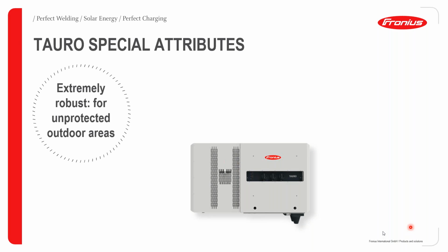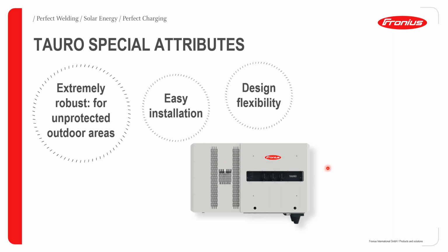So what can we say about the Tauros as far as the special attributes are concerned? Just to highlight for you, first of all, the Tauros is extremely robust, and this is for unprotected outdoor areas. As I mentioned before, the design of the Tauros inverter is very different from the SnapINverter series. The front cover, or the front area, is a double layered kind of design, whereby this inverter, even when you operate it under the exposure of sunlight, can continue to give you maximum power output without derating. Also, ease of installation and design flexibility.